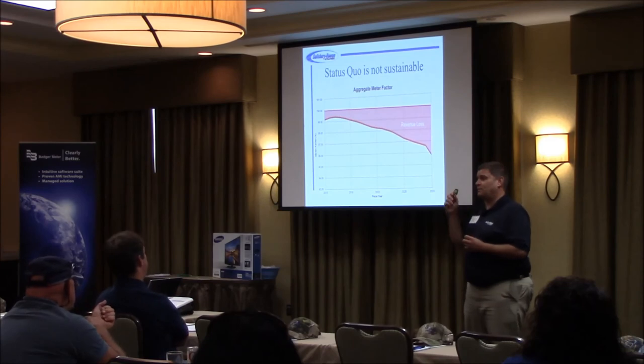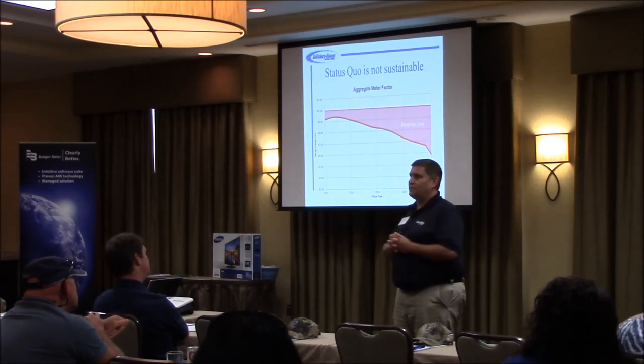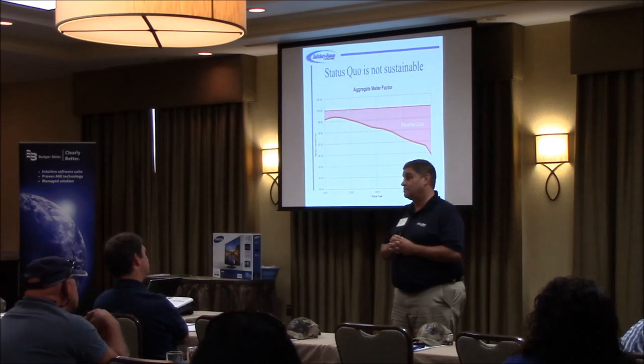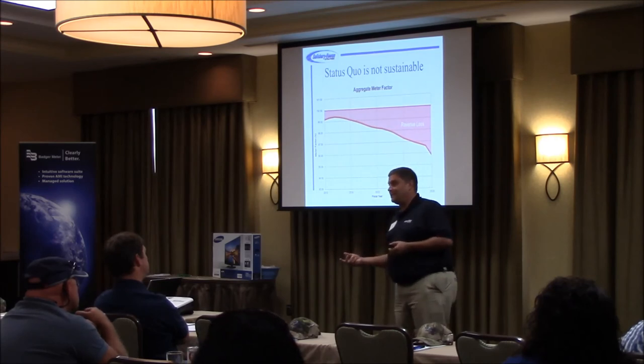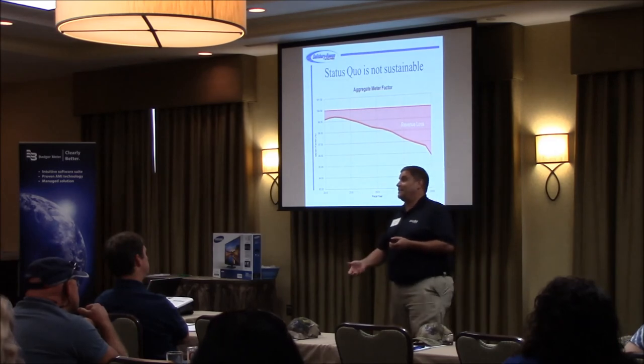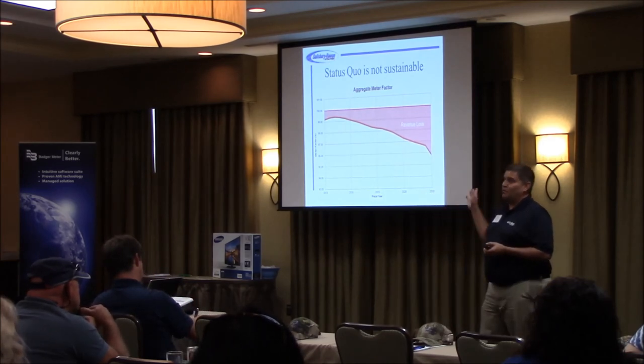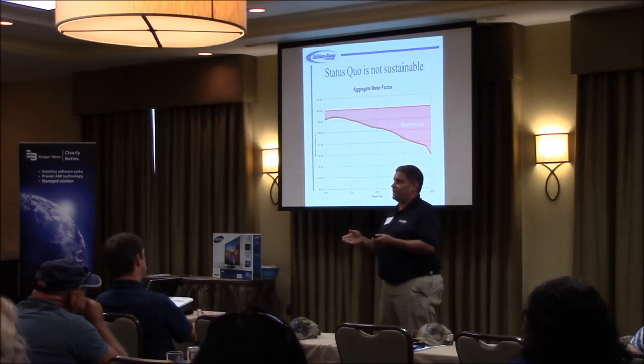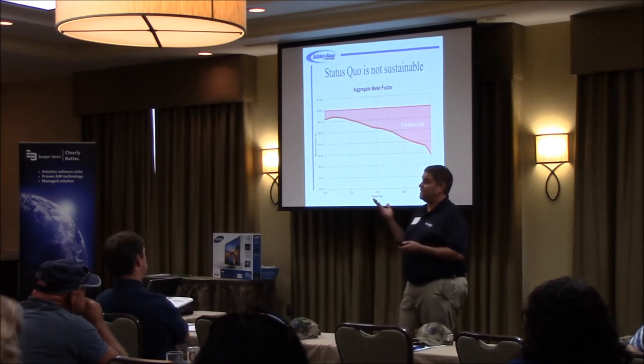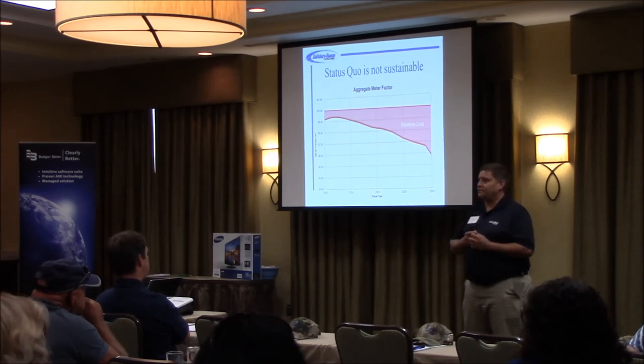And one other reason that we really decided on the E-Series meter, and Maurice did not mention this, is that with the tamper alarm on the E-Series, you do get a dry pipe warning. With a mechanical meter, if the customer takes the meter out of the setter, you don't ever know, as long as they get it back in before the meter reader comes back up. They can straight pipe, whatever. With the E-Series meter, because the speed of sound changes whether it's in water or in air, it gives you that dry pipe error, so you know when somebody takes that meter out of that setter. That was one of the big things that did it for us, all other things being equal.